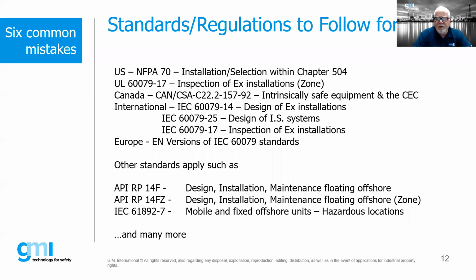Some other standards you might run into when doing design work include API recommended practices, commonly used in the offshore market. There are also other IEC standards, such as the 61892 series, which deal specifically with mobile and fixed offshore units. Hazardous locations is covered by the -7 standard, with references to intrinsic safety in all of these as well.